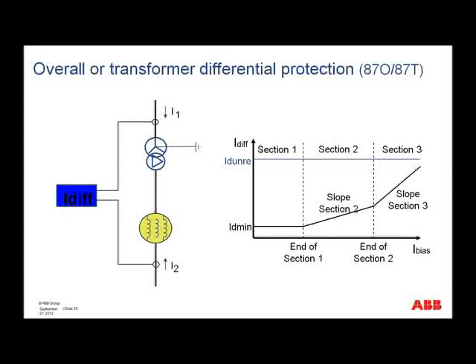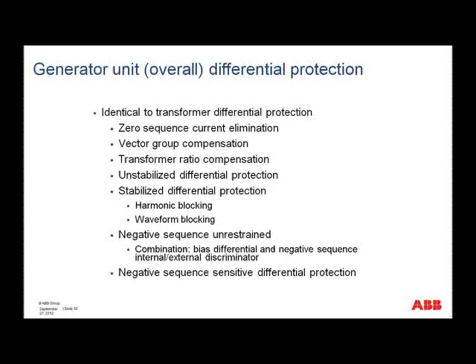So here we just have a look a little bit more at this 87O function, or as I said, 87T. And you can see that it has pretty much the same characteristic as what we saw for the 87G. And really the only difference is maybe there's the need to set this ID min a little bit less sensitive than what can be set for the 87G. So we're talking about maybe somewhere around the 30% mark. But as I said, otherwise it's really identical to an 87T, which we are calling 87O, in that it has to handle the transformer, which means that it has to have the capability to do the zero sequence current elimination, the vector group compensation, and the transformer turns ratio compensation.